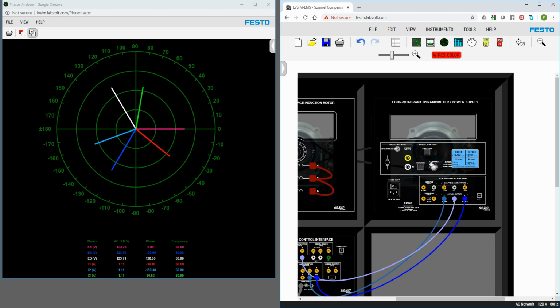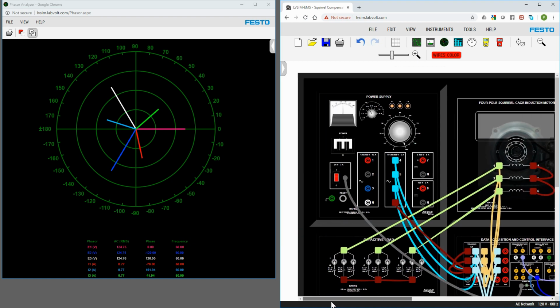If you are in an industry and you're having a bad power factor, they will charge you a very heavy penalty for that. Let's go back to a zero load. What I could do is add capacitors in parallel to that motor. For example, if I turn on the smallest capacitor in each of these, I see that the vertical part of my vector is becoming smaller because a capacitor is in fact a positive vector. So if you add a positive value to a negative value, they cancel one another.